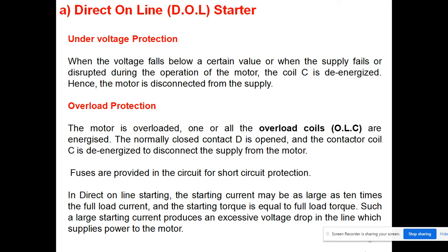In direct on line starting, if we are not using a starter, then what is the problem here? The starting current may be as large as 10 times the full load current, and the starting torque is equal to the full load torque. Such a large starting current provides an excessive voltage drop in the line which supplies power to the motor. So we want to avoid that here.